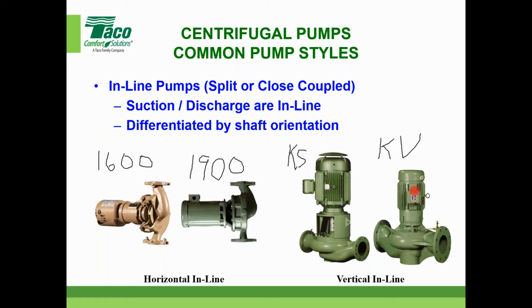Something to consider. Most of us understand that this model costs a little more than that one because there are more components. But I wouldn't go much higher than 7.5 horsepower, same as I said on the CIs. Some of my reps break it off at 7.5, I've heard others say 10. Engineers should think about the whole project, and from a maintenance standpoint, if you start specifying a KV with a 20 or 30 horse motor, sooner or later someone's going to have to jerry rig that to get it out. With the split coupled version, they can probably replace and change the seal without affecting the motor.